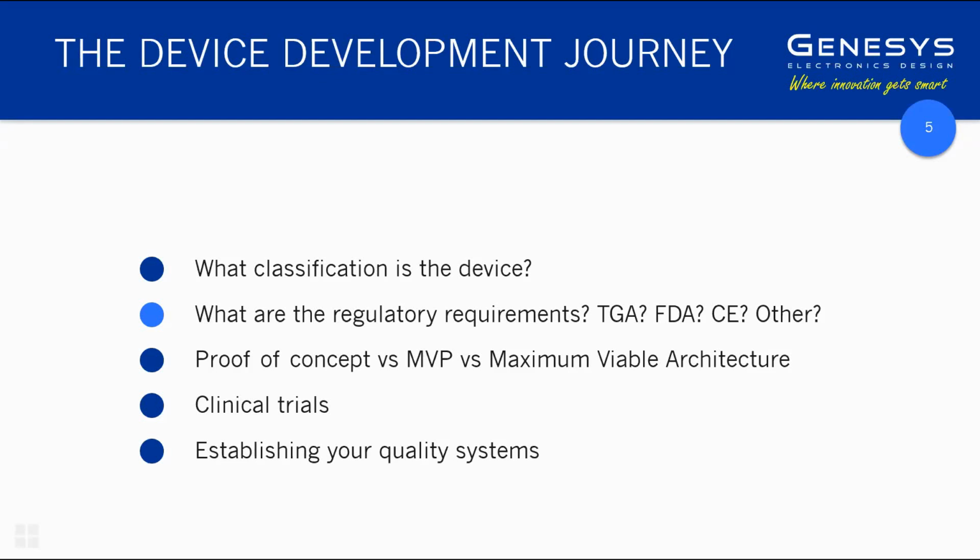And on the topic of clinical trials, I've had a number of occasions where a potential client has come to Genesys and said, we want to do a proof of concept to do clinical trials. The two terms are like oil and water. A more appropriate thought might be, we want to do a proof of concept to do some preclinical evaluation to prove that our bright idea is in fact something that's useful to the marketplace. But that is not a clinical trial. Clinical trials are undertaken on the market-ready product at the end of the process. And it's really important not to confuse the two.